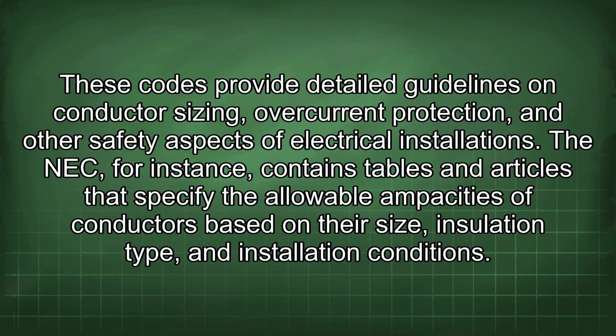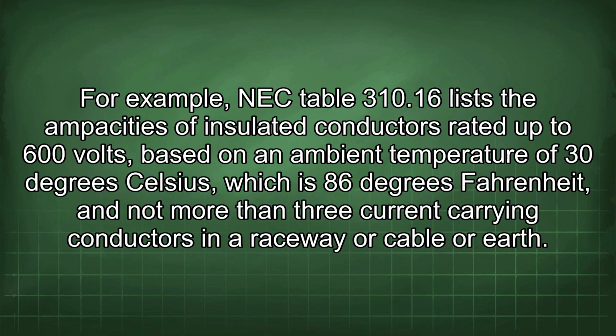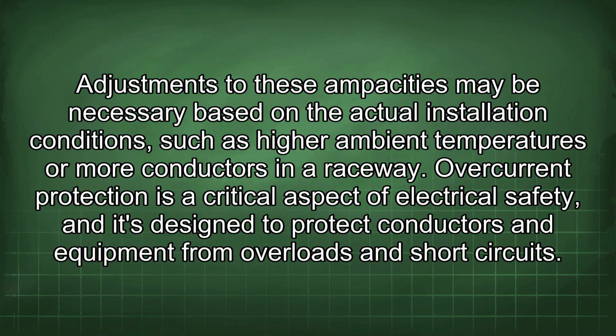The NEC, for instance, contains tables and articles that specify the allowable ampacities of conductors based on their size, insulation type, and installation conditions. For example, NEC Table 310.16 lists the ampacities of insulated conductors rated up to 600 volts, based on an ambient temperature of 30 degrees Celsius, which is 86 degrees Fahrenheit, and not more than 3 current-carrying conductors in a raceway or cable or earth. Adjustments to these ampacities may be necessary based on the actual installation conditions, such as higher ambient temperatures or more conductors in a raceway.